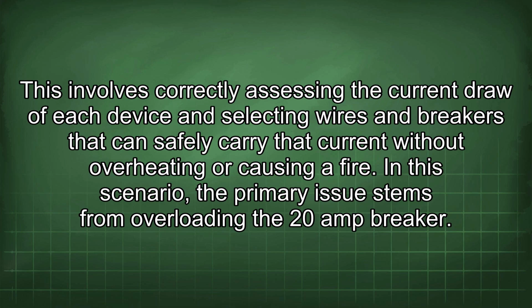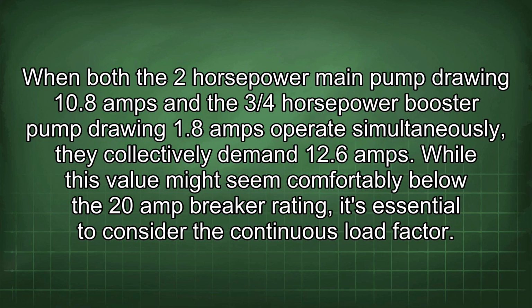In this scenario, the primary issue stems from overloading the 20 amp breaker. When both the 2 horsepower main pump drawing 10.8 amps and the 3/4 horsepower booster pump drawing 1.8 amps operate simultaneously, they collectively demand 12.6 amps.